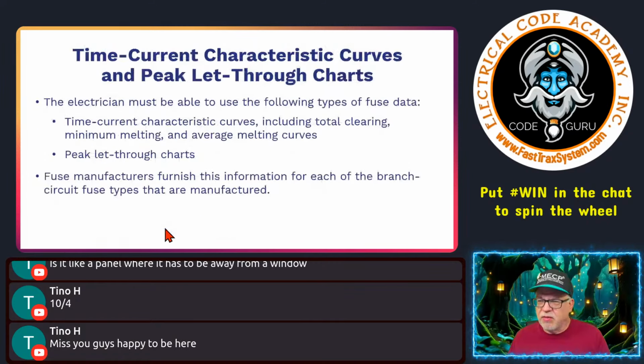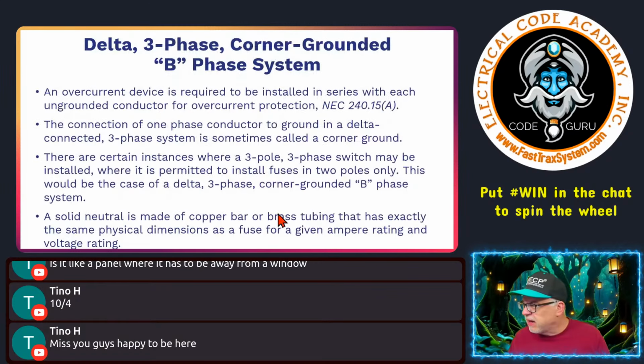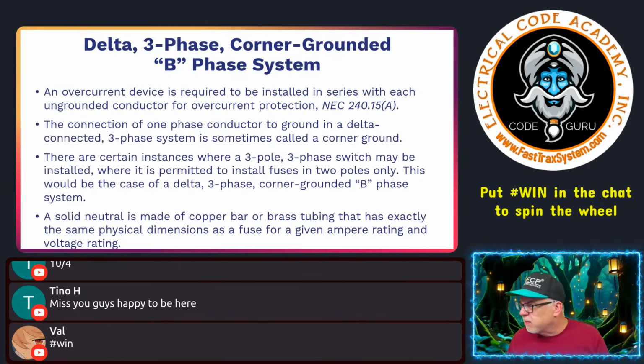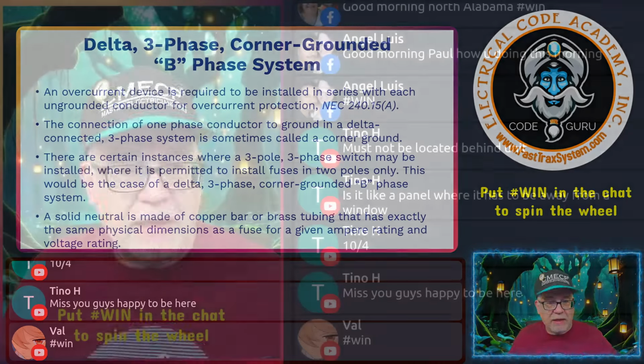I don't have an example of what it's talking about, but typically what we're saying is that most of the time when you get these panels that are made, the neutral is just a common bus, and you bring your conductors in. Now, here's what's interesting. The neutral is still breakable, okay? It's still removable. It can still be taken apart. It usually comes in and uses the bus to complete its chain.